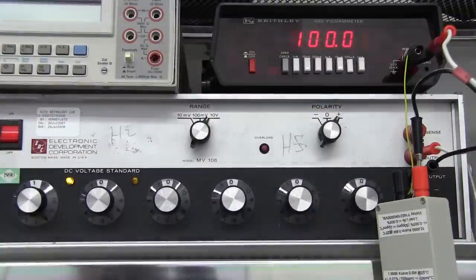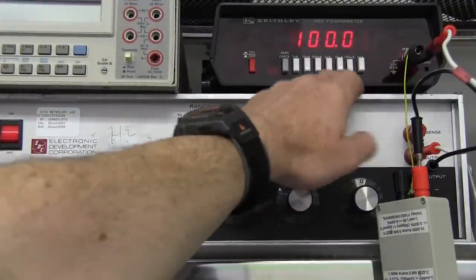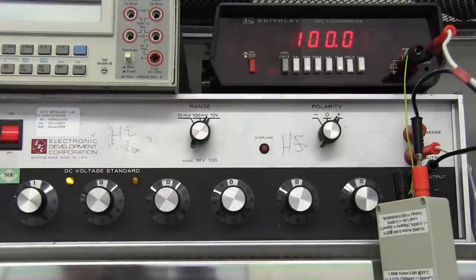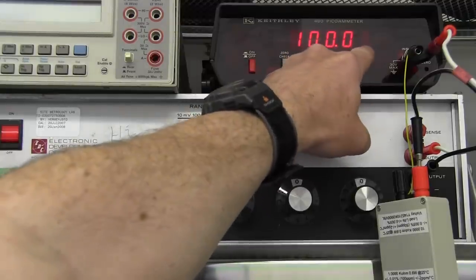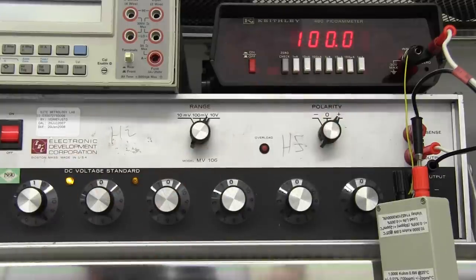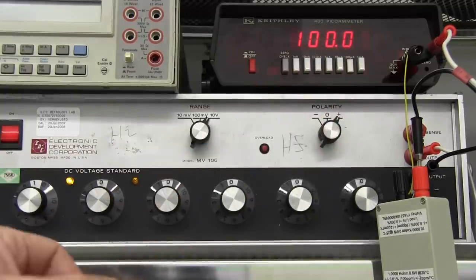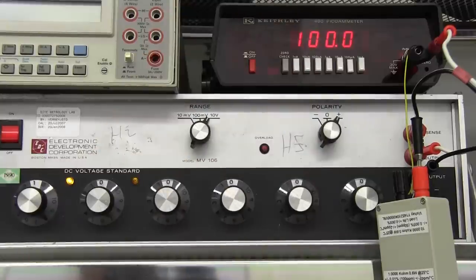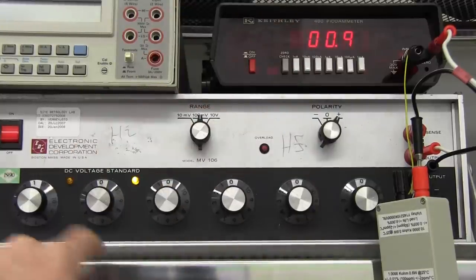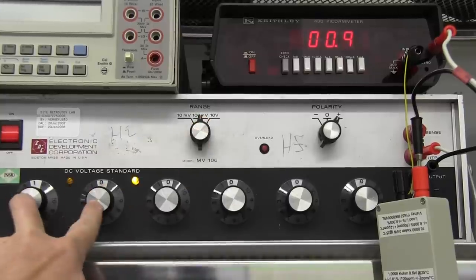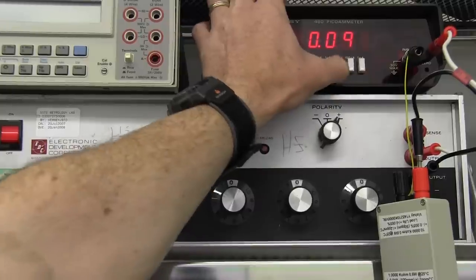So let's go up here. And we've got it set to 1 volt here, and we're getting our 100 microamps as we saw before, spot on. Because in theory, we should expect 99.99 microamps, but because that value is one digit better than the resolution we've got here, it's insignificant, especially when you consider the accuracy, or the intended accuracy, of this thing. But if we wind that down to 10 millivolts here, I'm on the 100 millivolt range, we're generating 10 millivolts.